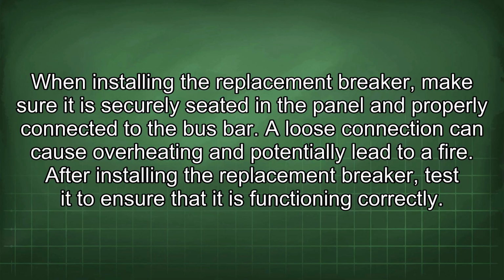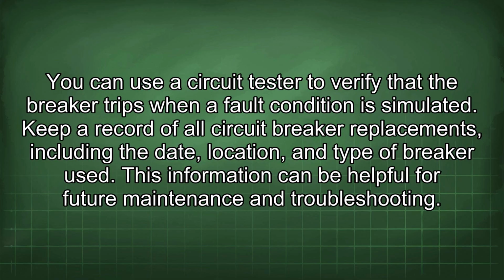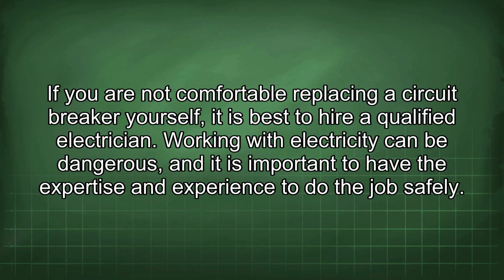After installing the replacement breaker, test it to ensure that it is functioning correctly. You can use a circuit tester to verify that the breaker trips when a fault condition is simulated. Keep a record of all circuit breaker replacements, including the date, location, and type of breaker used. This information can be helpful for future maintenance and troubleshooting. If you are not comfortable replacing a circuit breaker yourself, it is best to hire a qualified electrician.